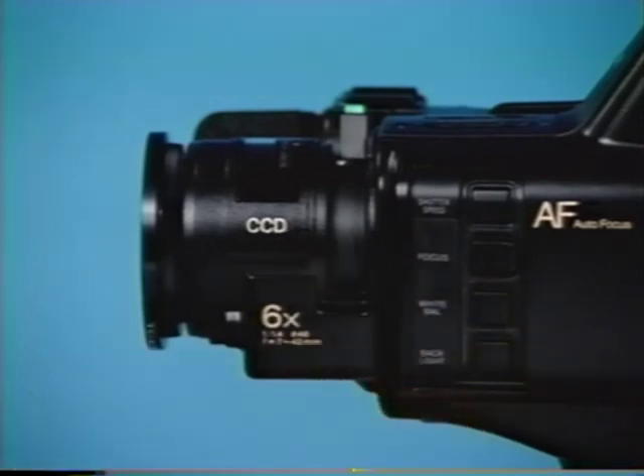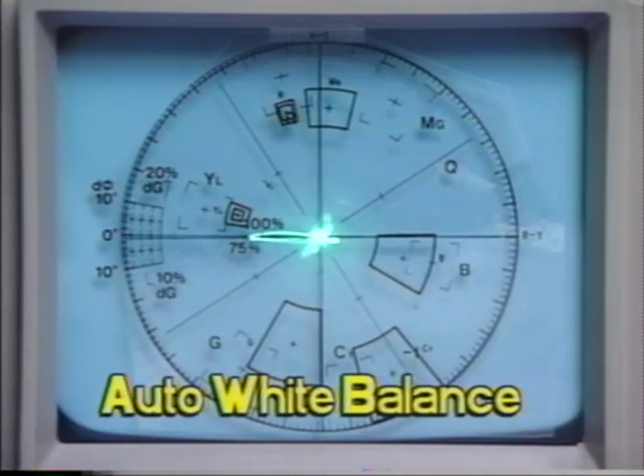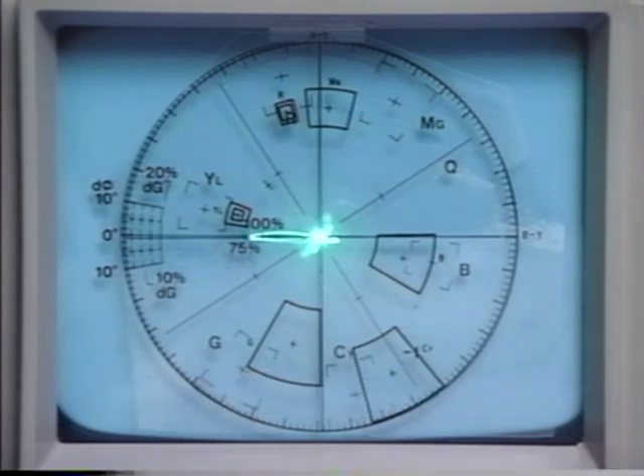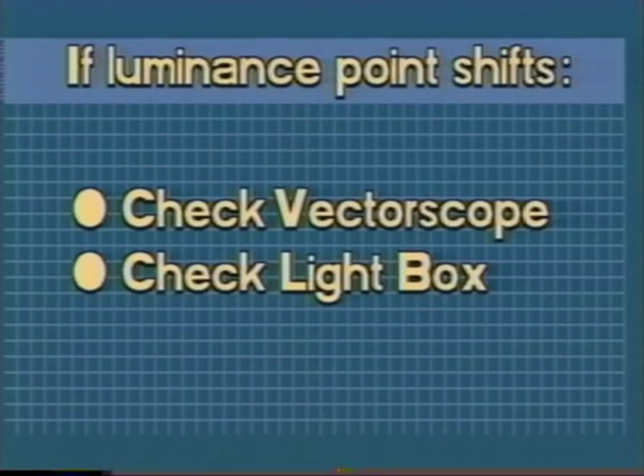Next, press the white balance button again to select the auto white balance mode. Again, confirm that the center of the white luminance point is in the center of the vector scope screen. If the luminance point shifts away from the center during any mode, recheck the vector scope adjustments and the lightbox calibration before judging that an alignment is required.